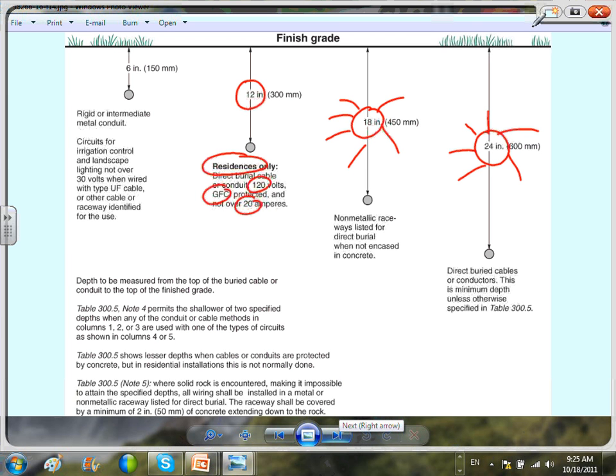Yeah. And the same thing with the conduit. What we do, guys, for conduit, if you have sharp rocks, is you bury your conduit, then you put an inch around it of sand or something soft, and then you put your rocks and all this good stuff. You don't want to damage the conduit or the cable as you bury it.